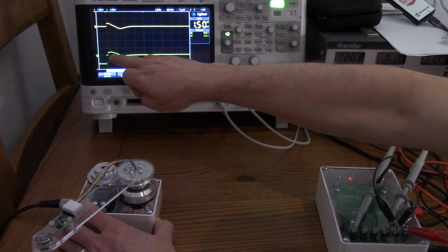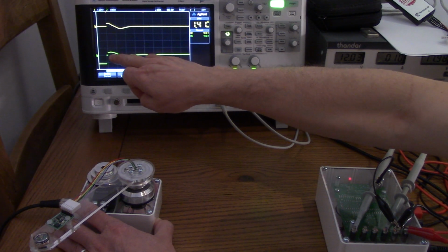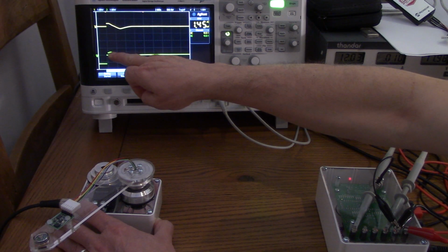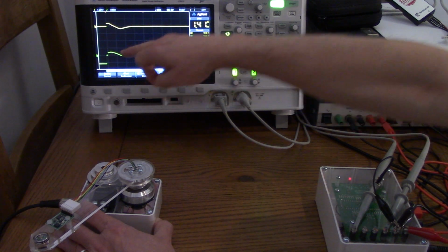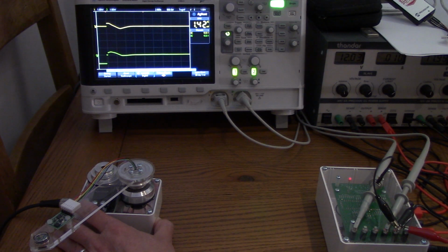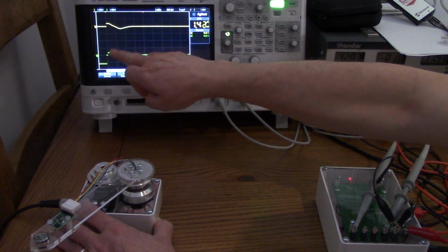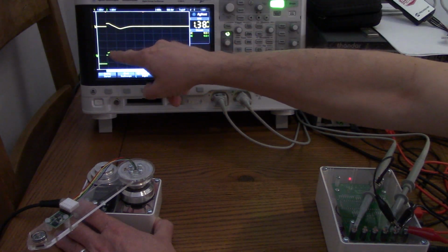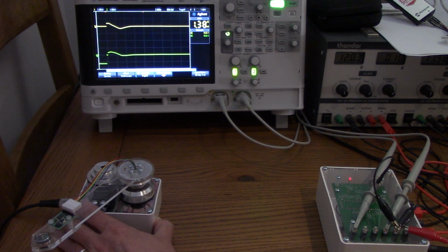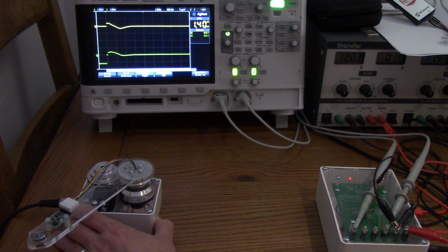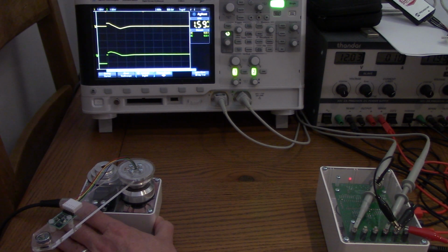So we're actually only sitting at, this is 1 volt per division, so it's not even that. Let's see, that's about 300 going into the servo. We need to look at that from a voltage perspective. So that's 300 millivolts, and you can actually calculate what the actual maths is for this drive here to see what the value is actually going into the servo itself. But it's actually a relatively small number. That's everything as regards the control.